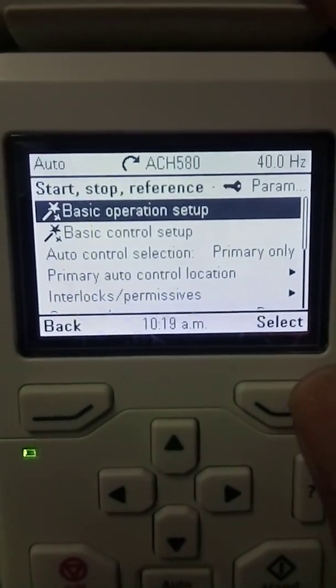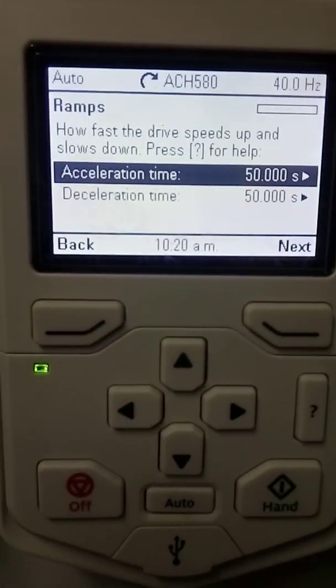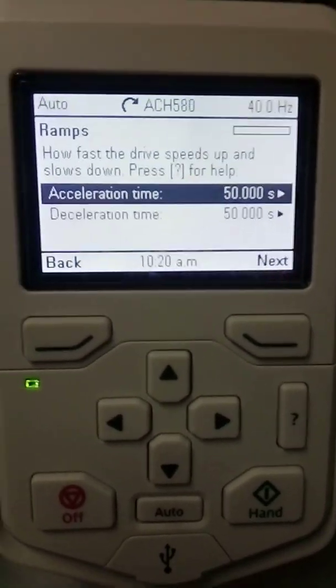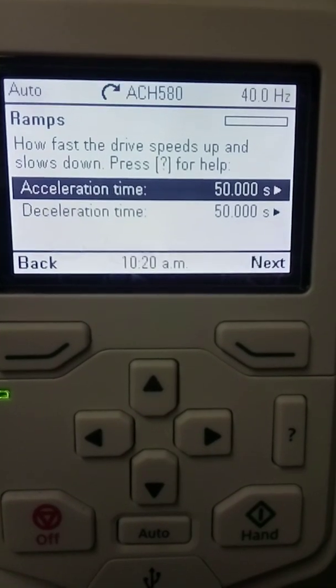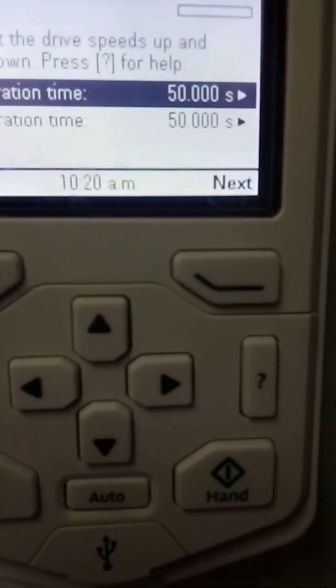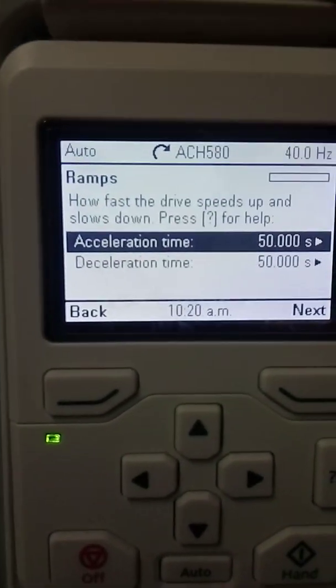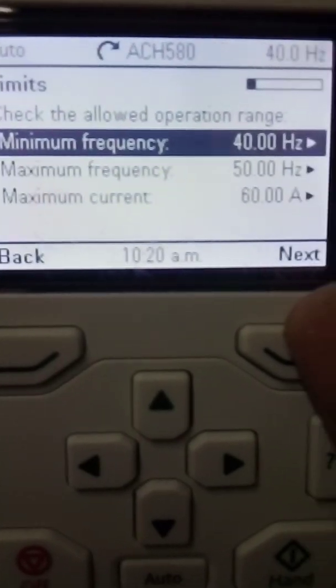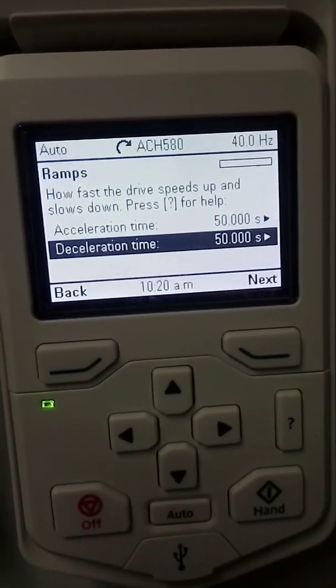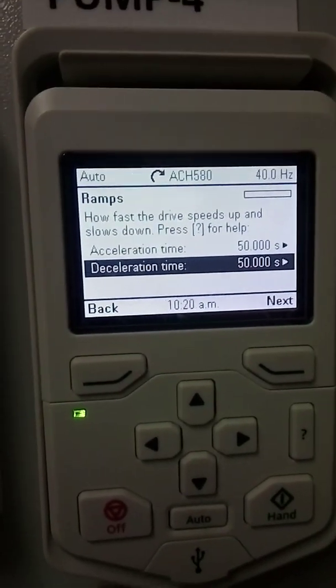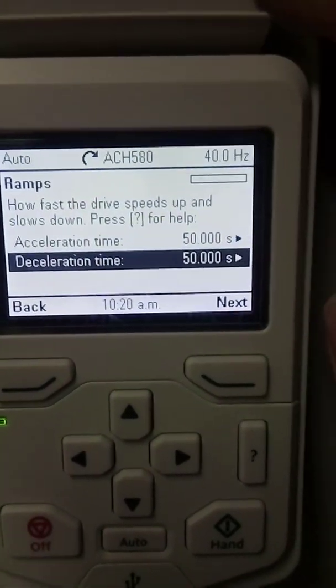Let's go to the basic operation setup. Acceleration time is the time when your motor will ramp up from zero to the high limit — from zero to 50 Hz. My acceleration time is 50 seconds. You can increase or decrease this setting; it's the factory default. If your drive is locked, you will be unable to change it. The next is deceleration time — once the motor receives the stop command, this is the time your motor will ramp down from high speed to stop.